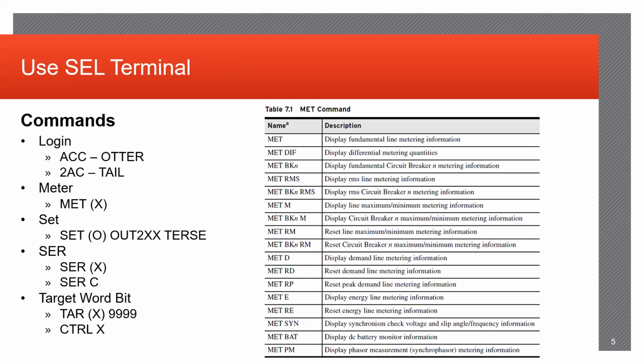Getting into the SEL terminal side a little bit, this is an extremely useful tool when testing, because it's a little bit complicated to begin with, but once you understand the commands, it becomes extremely easy to set up SER data, setting outputs, targeting bits when testing, et cetera. So some of the commands here shown are specifically related to the metering stuff. As you can see, there's a lot of metering commands associated that may be used for different purposes.